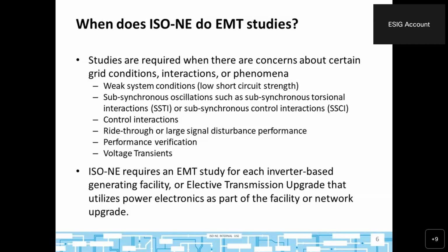For SSTI and SSCI, we're making sure that the IBR's control designs don't adversely interfere with other nearby resources or cause any sort of high frequency oscillations. If a control design is poorly designed, it can push and pull against other resources and cause oscillations. From the synchronous generation world, most folks would probably refer to it as hunting.